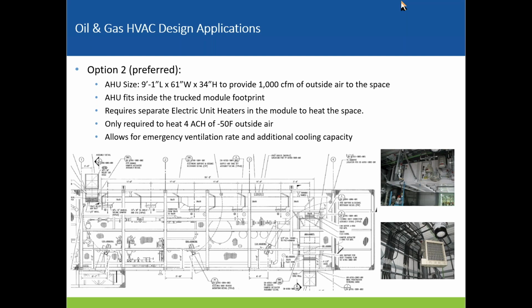So is the 1,000 CFM based on the 12 air changes? The 1,000 in this example is based on the 4. So your total airflow coming through this module is twice what the airflow would be in the other module. So it allows you to add some additional cooling capacity in the summer. So it's a 3,000 CFM unit. And then it also allows you to bring in emergency ventilation rate on gas detection, which provides a little additional layer of protection.